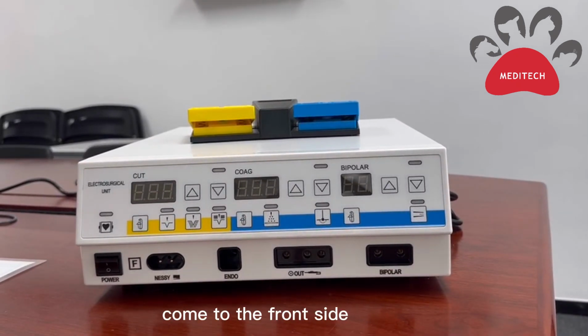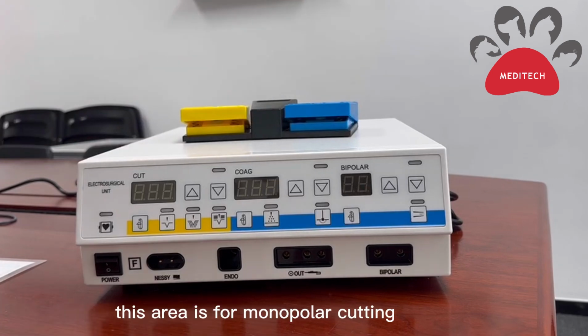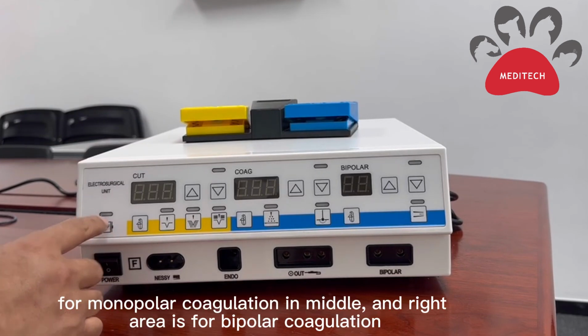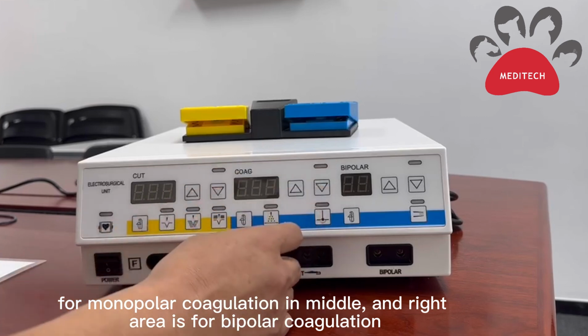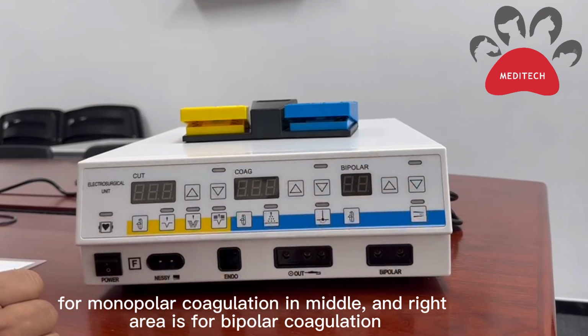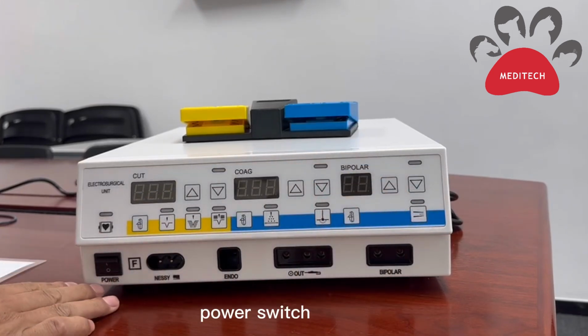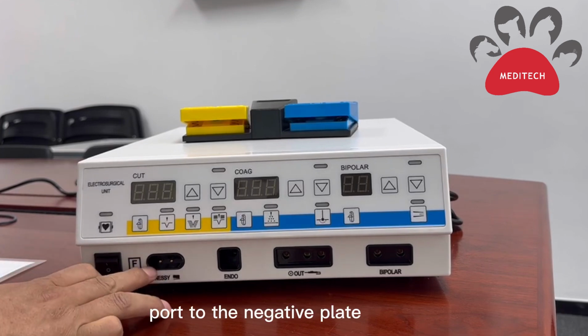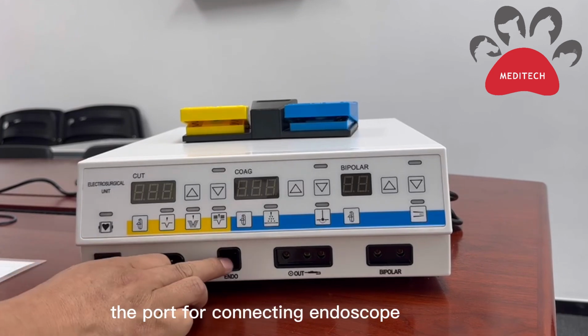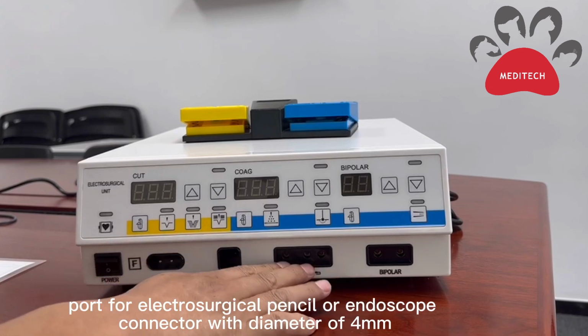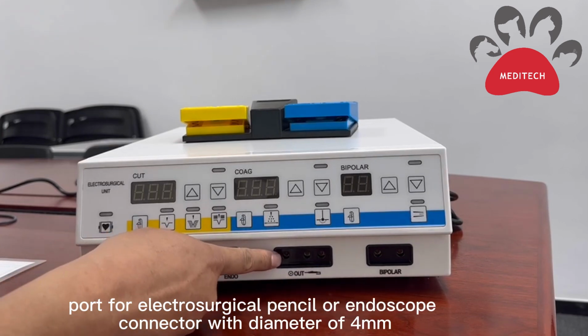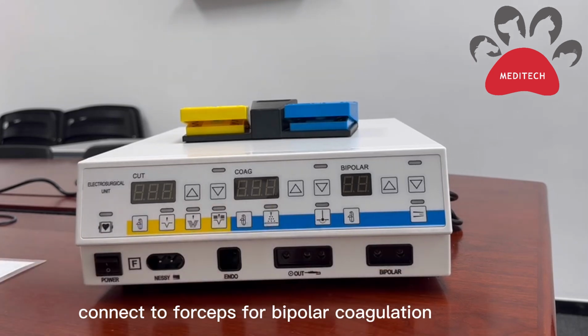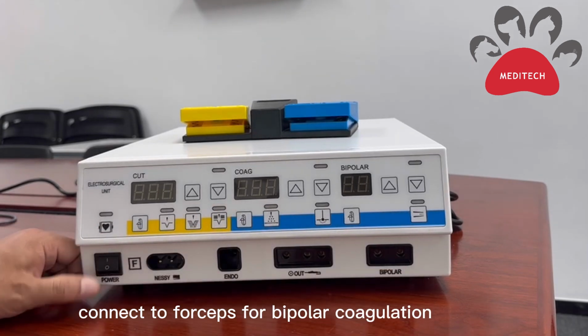Come to the front side. This area is for monopolar cutting. For monopolar coagulation in the middle, and the right area is for bipolar coagulation. Power switch. Port to the negative plate. The port for connecting endoscope. Port for electrosurgical pencil or endoscope connector with diameter of 4 mm. Connect to forceps for bipolar coagulation.